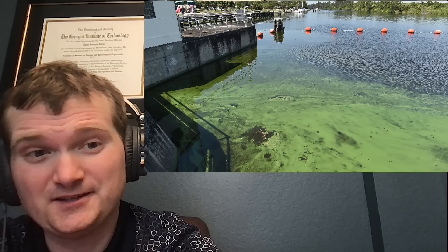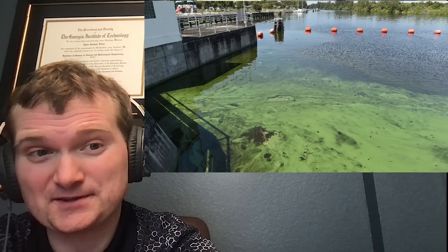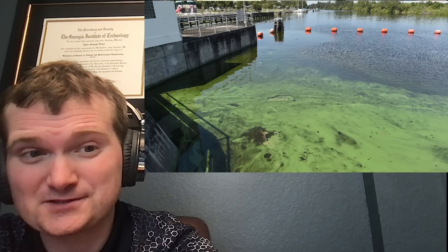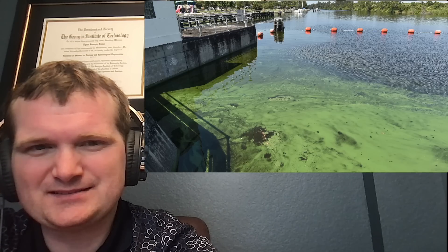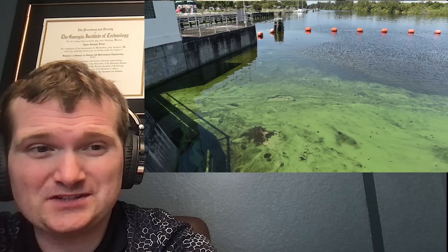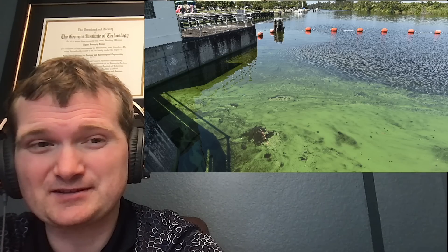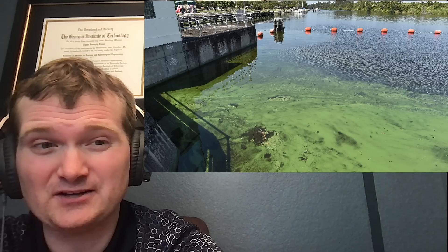One other reason why you would have something to get rid of sunlight would be to prevent the growth of algae. I know this is water that's also chemically treated. At least at a nuclear plant's cooling reservoir, I've seen algae blooms — they look kind of like this. A lot of people associate green glowing things with nuclear things, and seeing this green stuff by the circulating water intake structure that sends water to cool the condenser can be kind of funny. The main hazards associated with this to the plant are long-term biofouling of heat exchangers, and again, this is all in the non-nuclear part of the plant. They are chemically treated, usually by something like copper sulfate. I also wouldn't recommend swimming in an algae bloom, depending on the species of algae — that can produce toxins.